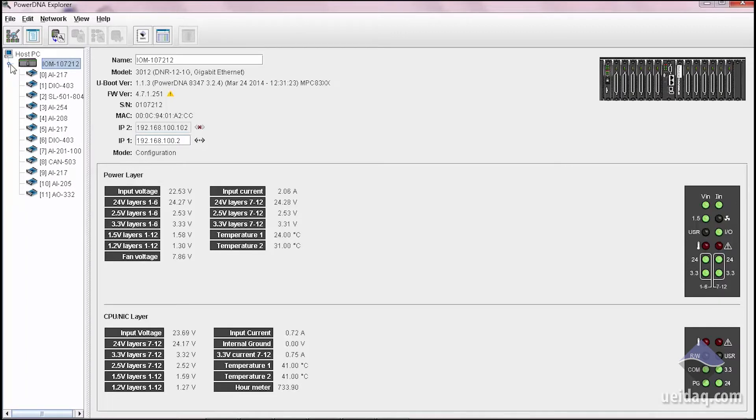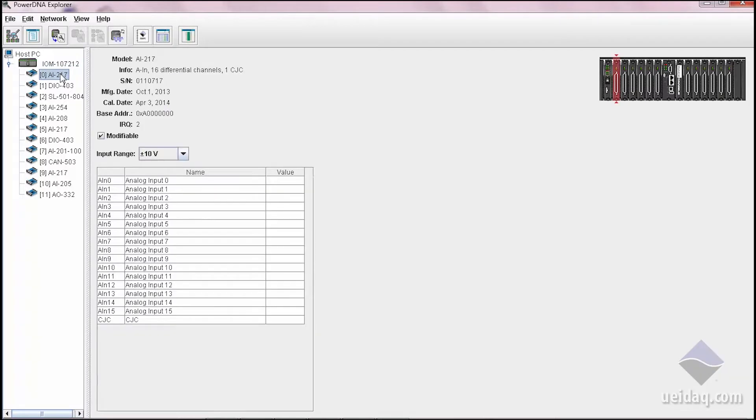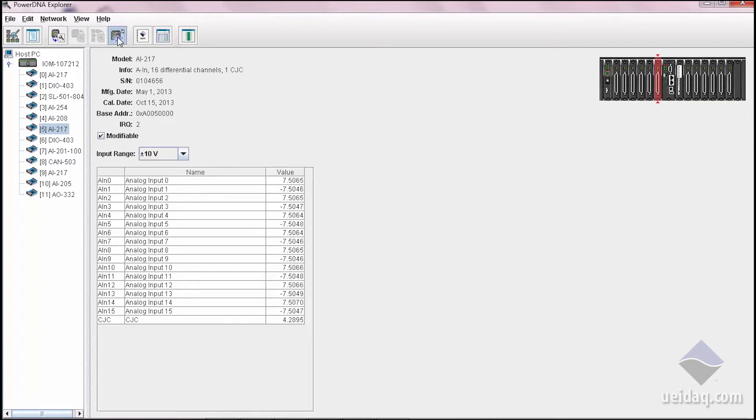If you'd like to exercise an I.O. board, you simply click on one, go to this one, and I can start data acquisition. I have a loopback dongle attached, so you're going to see alternating 7.5 minus 7.5 volts.